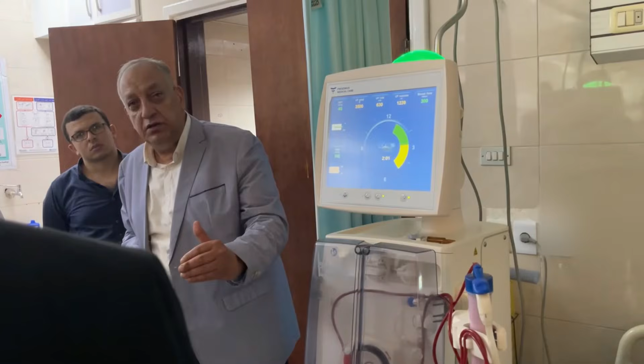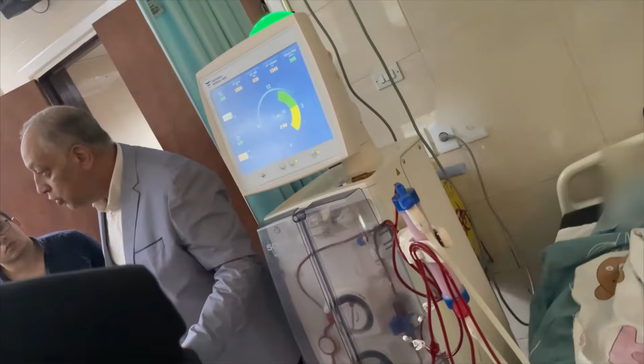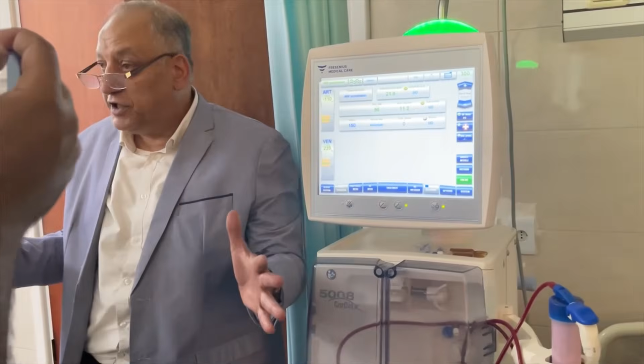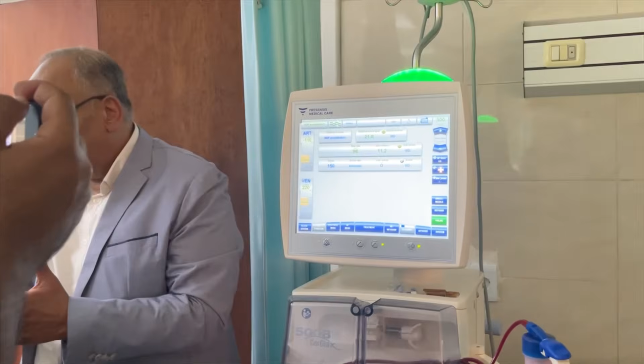If you are increasing above 25, the machine automatically calculates the dose according to the safety of the extracorporeal surface. So you have an automated mode and a manual mode. If you change the automated mode into the manual mode of hemodiafiltration, you will be clearing the clog of the pores in this substitution. Another way is back filtration on demand. When the transmembrane pressure increases, the machine stops ultrafiltration and starts to push dialysate from the outside to inside, exactly the opposite of ultrafiltration, back filtration on demand, on requirement, depending on the transmembrane pressure.